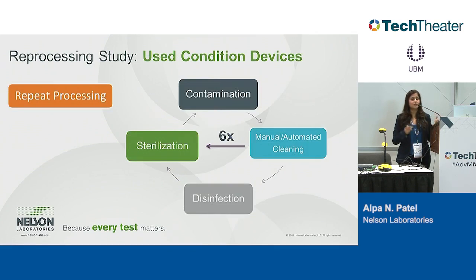Now I'm just going to go over some of the concepts of a cleaning validation from the document that I just showed you. I think it was about 5 years ago when the FDA came to us and said validations on newly manufactured devices will no longer be acceptable. You would have to perform validations on used condition devices because these are reusable and they do get reused over and over again, so we want to see them in used condition. Now, when you're manufacturing a new device, you don't have them in used condition unless you've used them for clinical trials, and you can use those devices and provide a justification to the FDA.